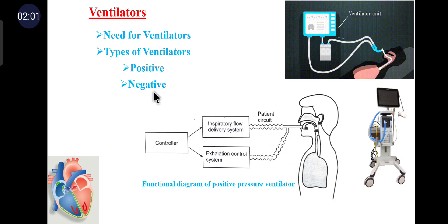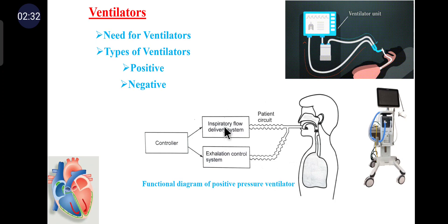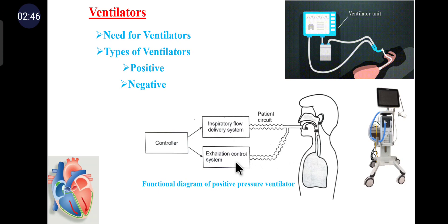Negative pressure ventilators are not preferred due to some technical reasons. In the positive pressure ventilator, inspiratory flow is achieved by applying a positive pressure greater than the atmospheric pressure to the airways. During inspiration, the inspiratory flow delivery system creates positive pressure in the patient circuit and the exhalation control system closes the outlet to the atmosphere. During the expiratory phase, the inspiratory flow delivery system stops and the exhalation system opens a valve allowing exhaled air to the atmosphere.